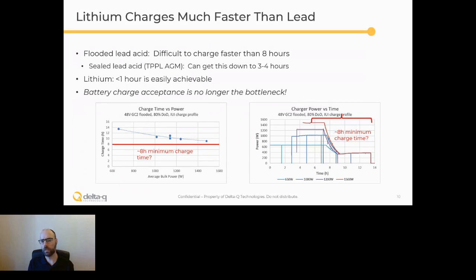And this is really baked into the chemistry of lead acid batteries, that particularly when they're used in a deep cycle application, in a traction application, they need to have 10% more amp hours put in than are taken out. So they need a charge return factor of about 110%. With flooded, maybe 105% or so with sealed batteries. And that finish current, that extra 5 or 10% charge return, is what you're seeing in that finish phase.